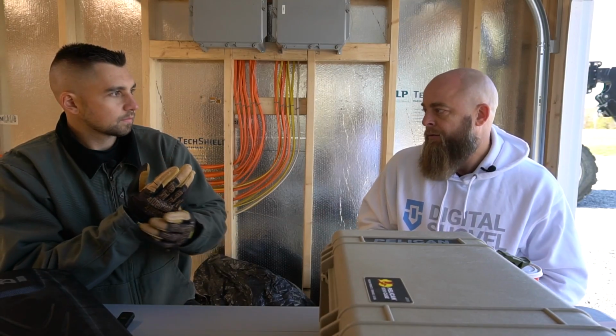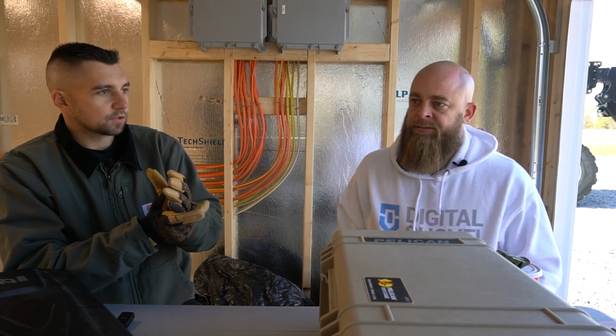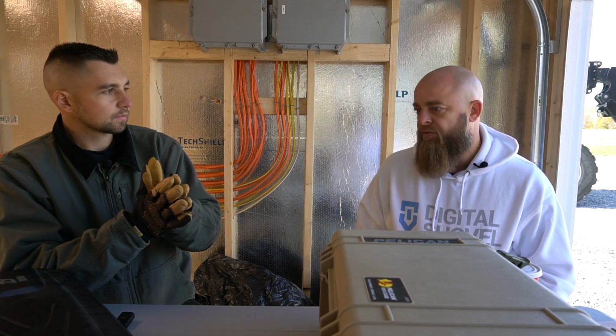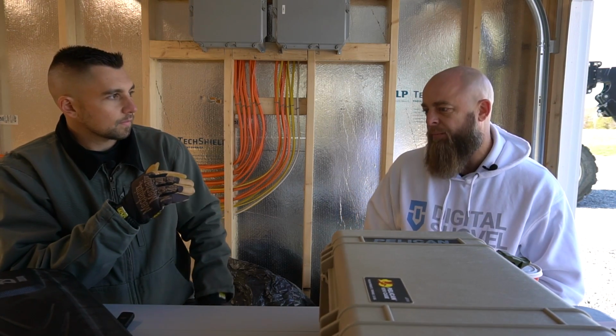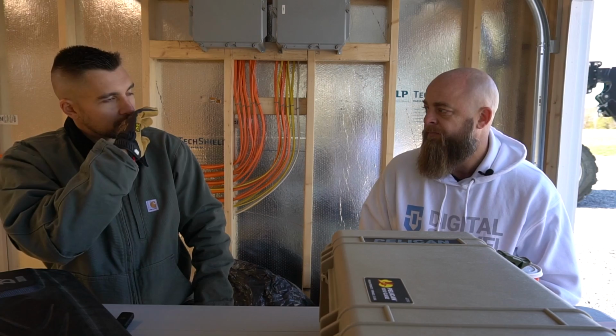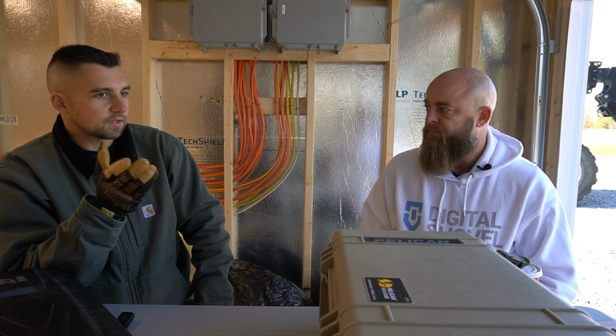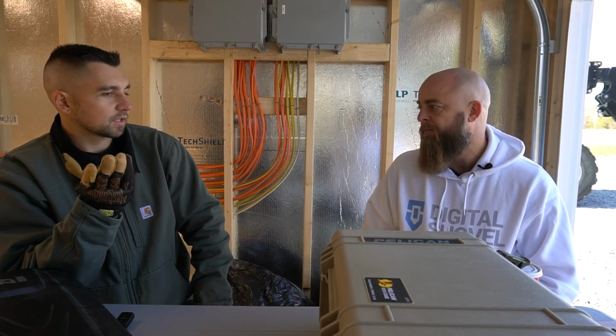So you have 416 usable amps - that's actual power, not with a 20% derating. So essentially it's like a 500 amp deployment with the 80% rule.